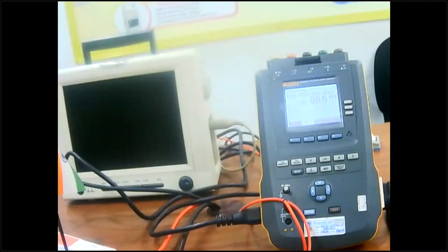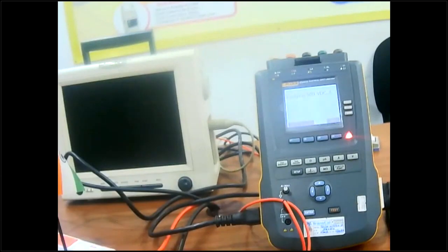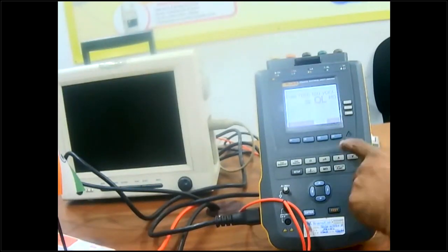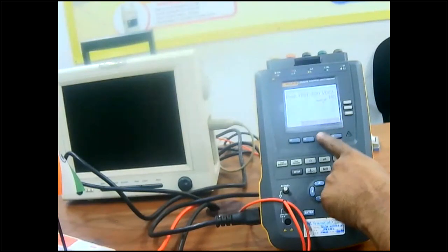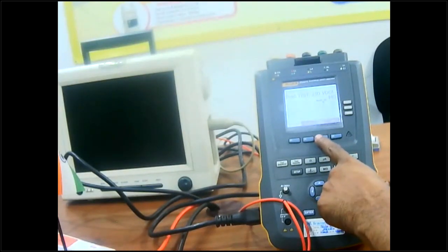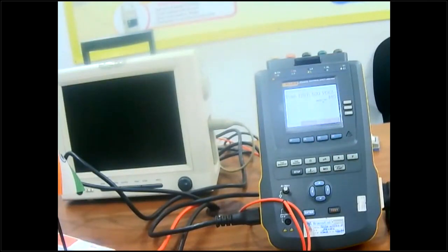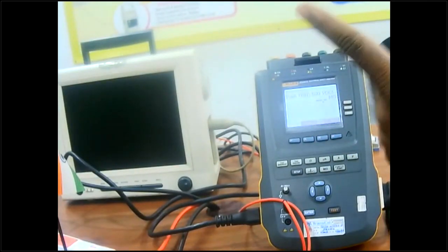Okay, next is mains on applied parts. Mains on applied parts is acceptable because it is having a very good reading. Another thing I wanted to tell you, you can change the voltage to 500 or 250. And next test, now actually I have done it on the protective earth.